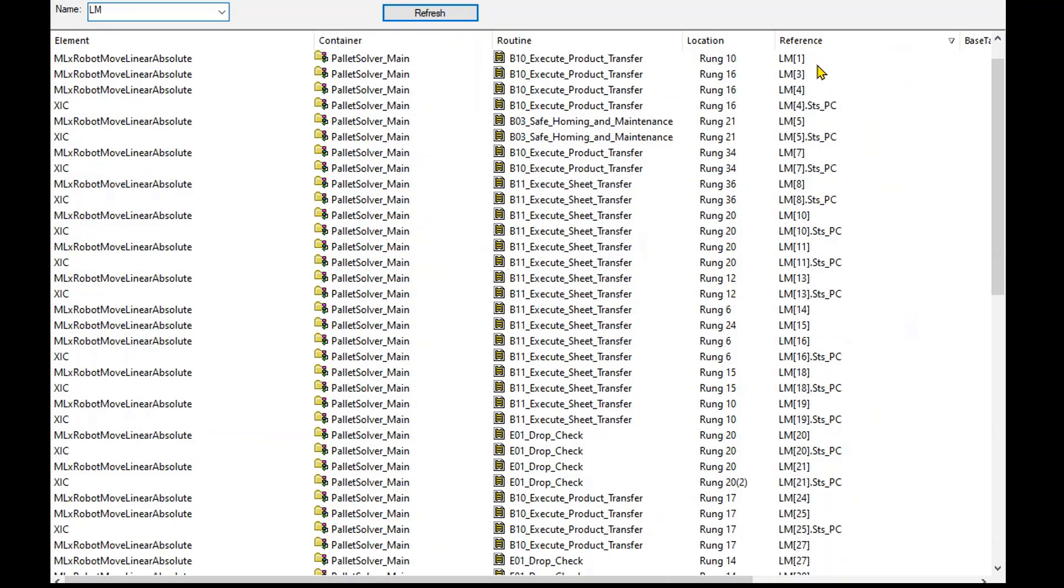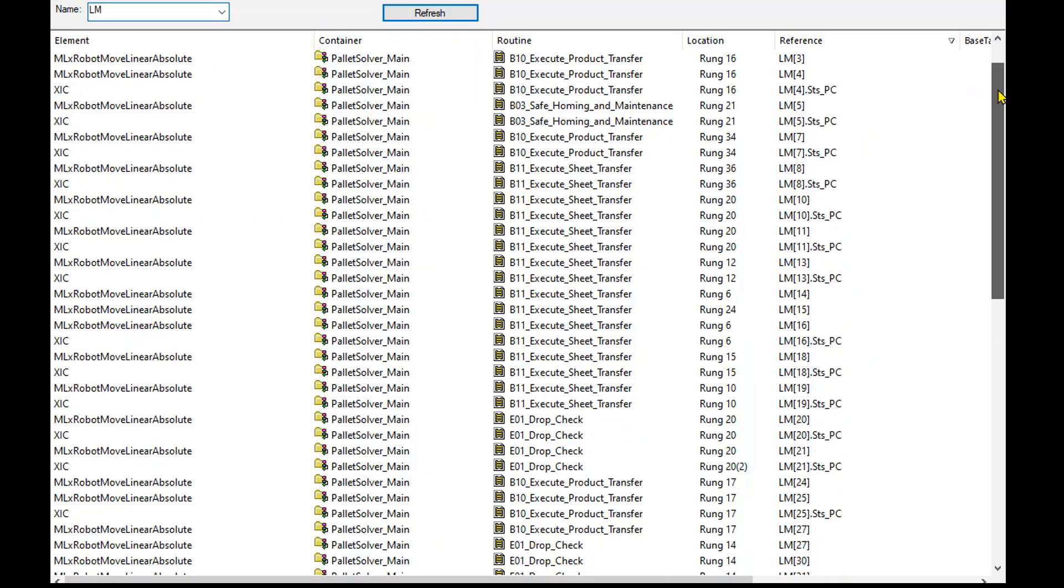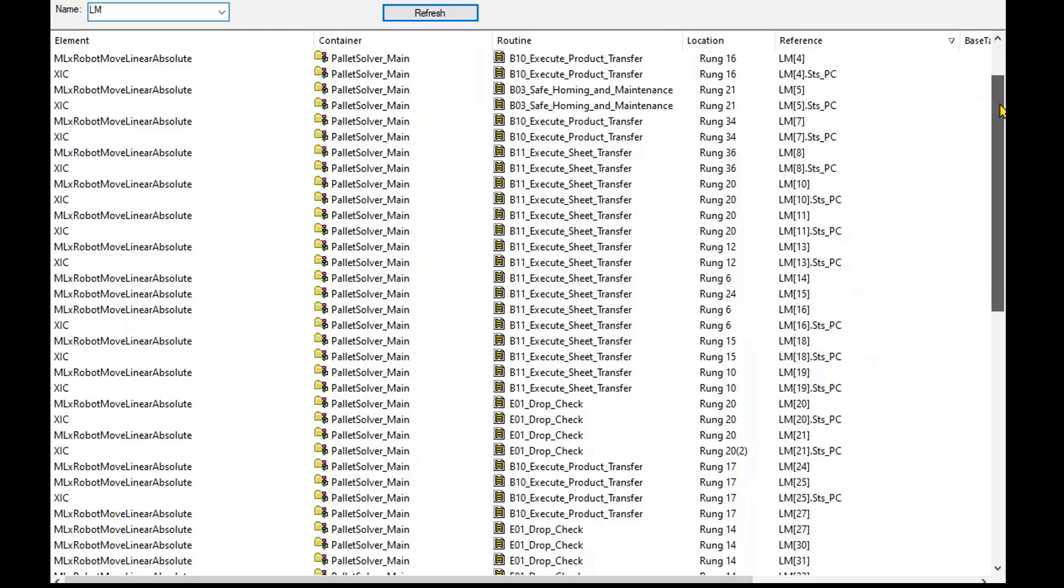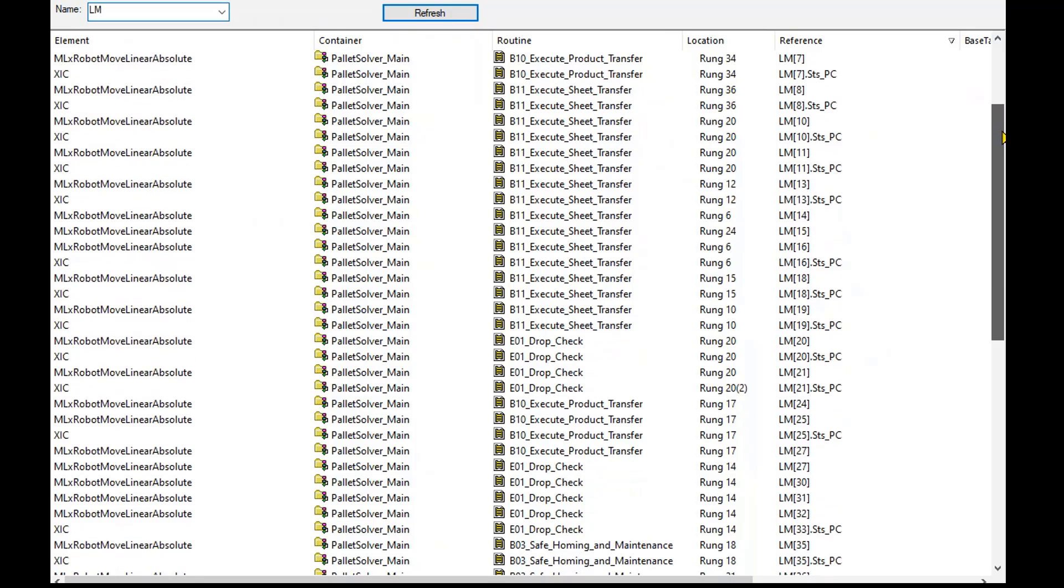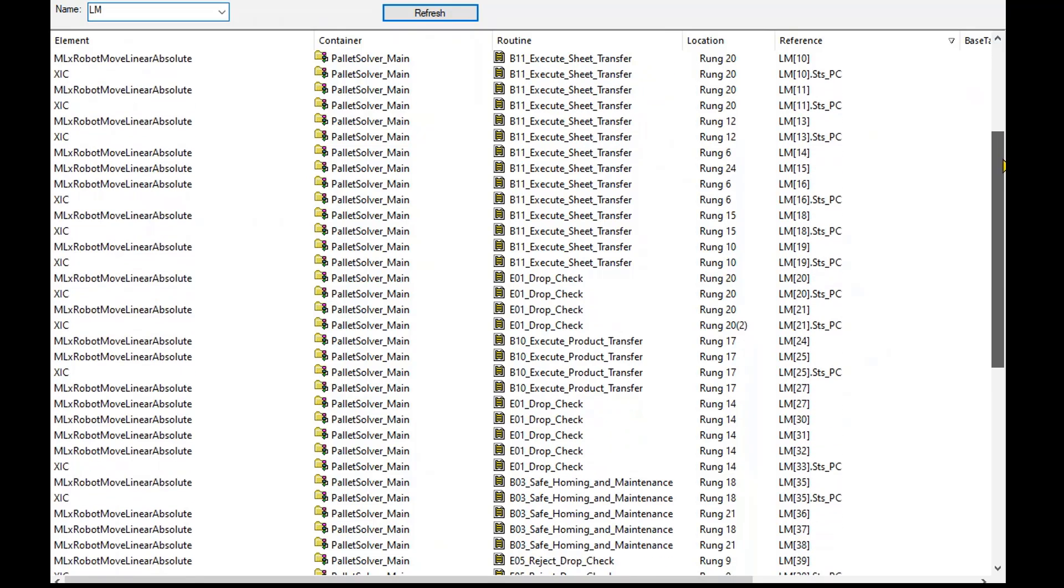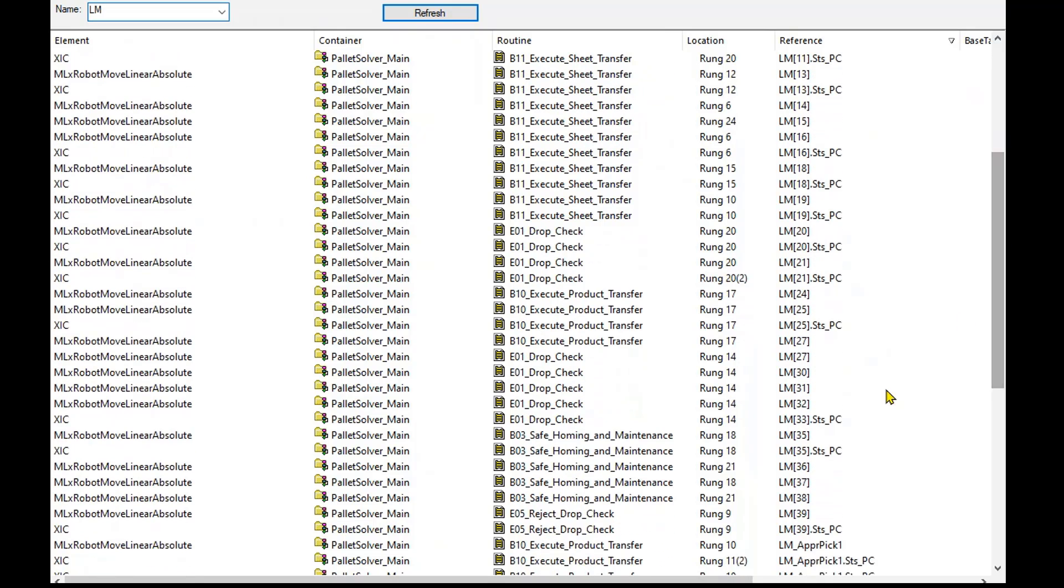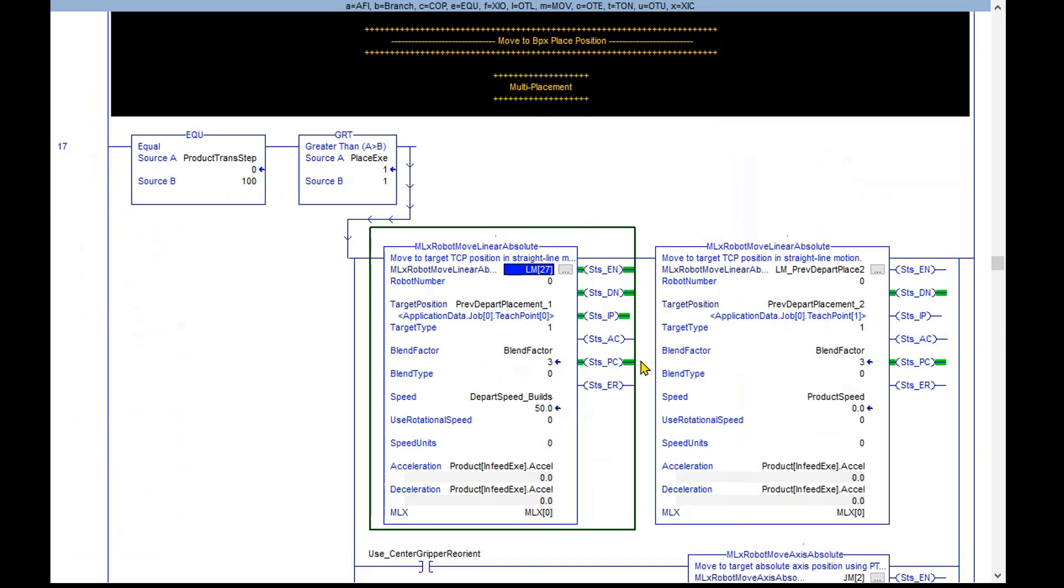Let's sort them to make it easier to check for a double occurrence. Let's look at the ones that are actual AOI commands. Some of them will be command status bits. Now you can see that LM27 was used twice and this is causing the issue. To fix this, look for a number that's unused like 28 and change one of these to that new number.